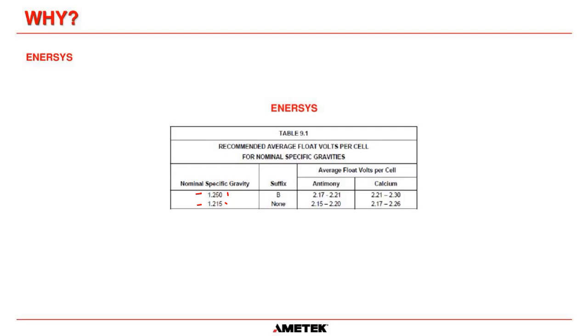And just to confuse things even more, the makeup of the plate inside the cell, because they're not all pure lead, there's usually a frame, and the alloy of the frame of the battery could be antimony or it could be calcium, and that affects the float voltage as well. So if you have a 1.25 antimony battery, they're saying you need to charge it between 2.17 and 2.21 volts per cell. So if you take the halfway point, that's going to be approximately 2.19 volts per cell.